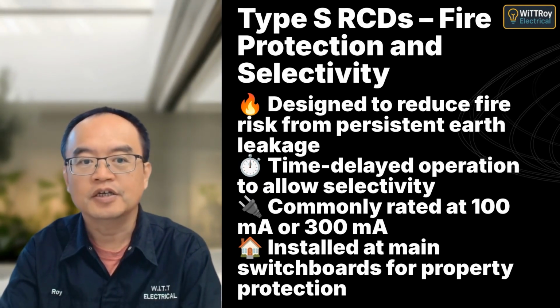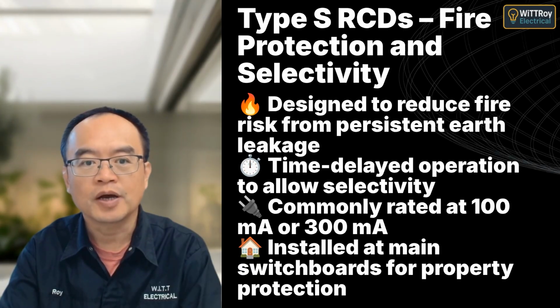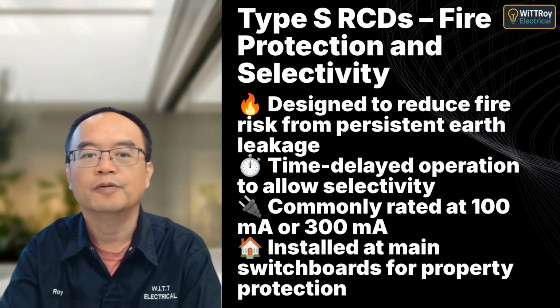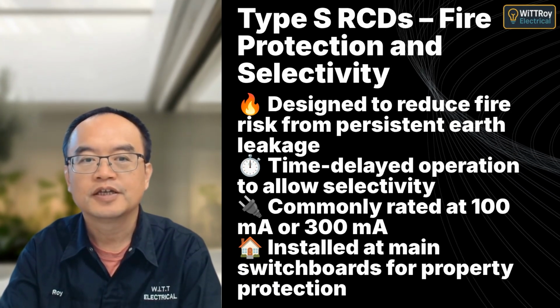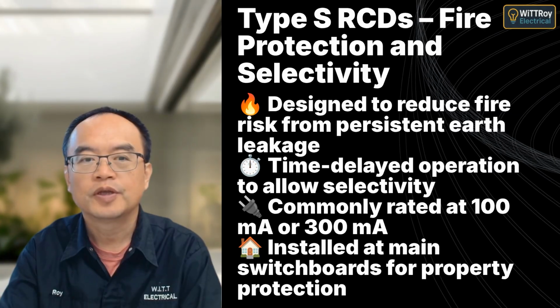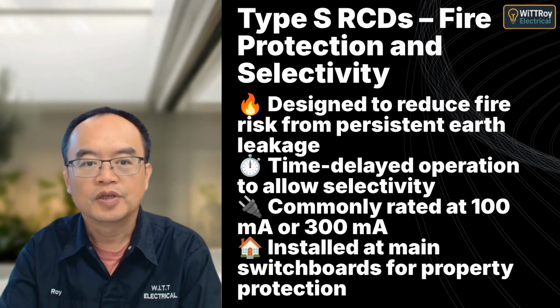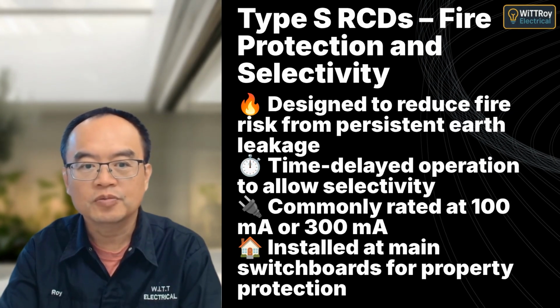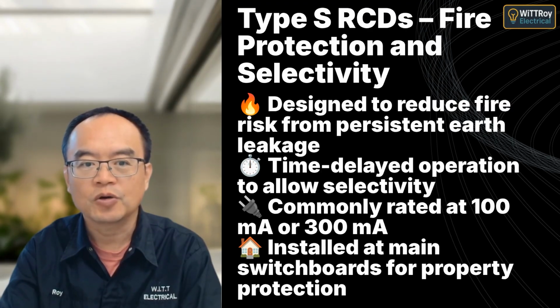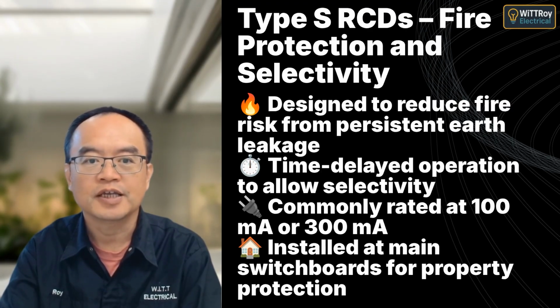Type S RCDs are time-delayed devices that trip at 100 or 300 milliamp to reduce fire risk from persistent leakage currents. Installed at main switchboards, they work with downstream 30 milliamp RCDs to provide selectivity and protect property from faults like smoldering insulation.